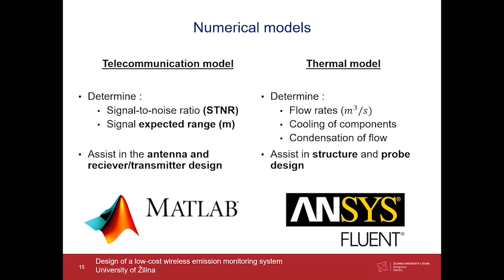The second model will focus on the thermal aspects. It is important to ensure that the air cools to room temperature before entering the device. Otherwise, the 200 degrees Celsius gases will permanently damage the sensors. This model will calculate parameters such as the airflow rate within the device, the condensation of the gas, or the temperature distribution within the skeleton. Just to emphasize, the temperature within the casing must not exceed 30 degrees Celsius.